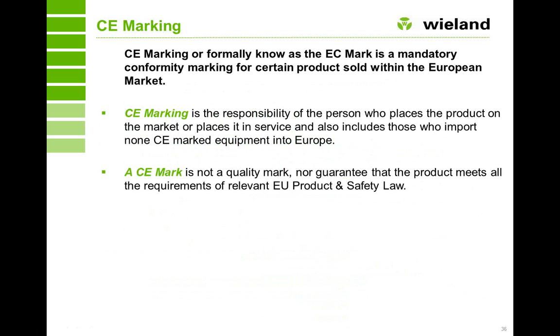It's the responsibility of the buyer of the machine to check and find out that you comply. So typically what you'd have on a CE plate as an example would be the year of manufacture, the type of machine that it is, any serial number, ident number, and you also have to clearly put on there the manufacturer's name and address and, where required, the authorised representative's name and address, in relevance to the standards. Now that is just a brief guide to the CE marking. There are other steps, and as we mentioned, we're more than happy to come in and discuss further with you.